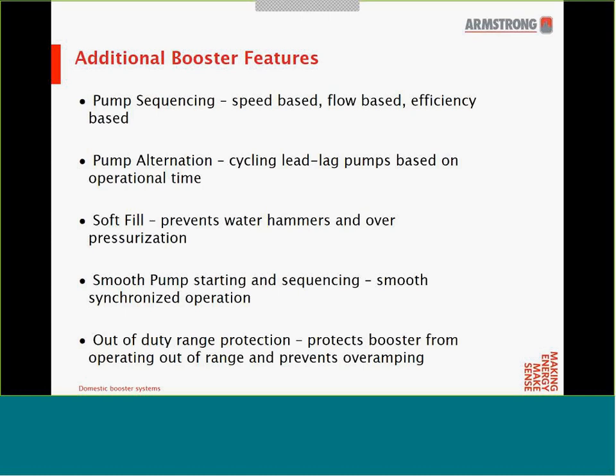The third feature is soft fill, which allows pumps to operate gradually when filling pipes at system startup or after maintenance. If pipes fill too fast, water hammers or over-pressurization can occur — filling slowly prevents these problems. The fourth feature is smooth pump starting and sequencing: when changing from one pump to two, the first pump ramps down slowly and the second ramps up slowly and harmoniously to prevent sudden spikes in pressure or vibration. The last feature is out-of-duty-range protection, which protects the pump in case of operating out of range and prevents over-amping.